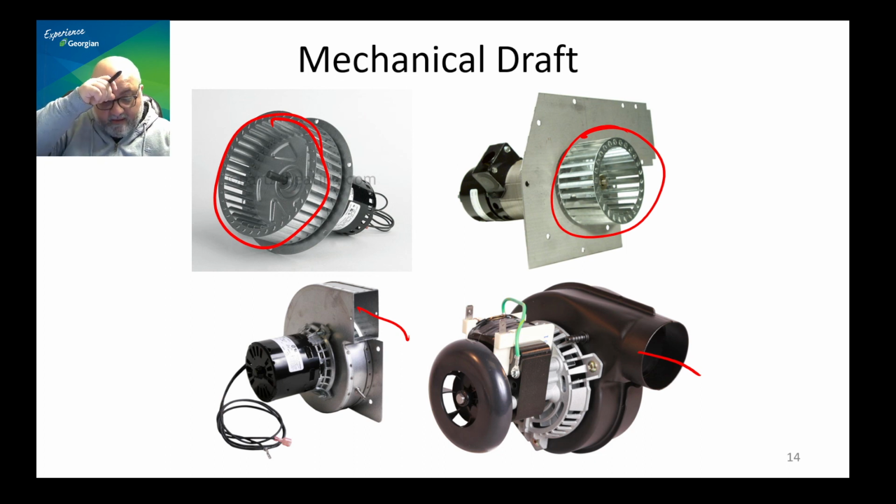I know for a fact that on a Carrier rooftop unit it could be up to 3600 RPM. So yes, it's going to break easily, and it's an easy job to identify a defective venter motor, because the rooftop unit is sending power to the motor and the motor is not running, or it's running very poorly.